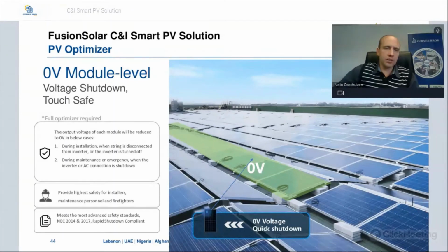Zero voltage module level voltage shutdown, touch safe. So you need a fully optimized system to have the 0 volt module level shutdown. On the Huawei system specifically, it's not necessary to optimize each panel if it's not a requirement, although the advantage of optimizing everything would be the 0 volt module level shutdown. So it provides the highest safety for installers, maintenance personnel, and firefighters.